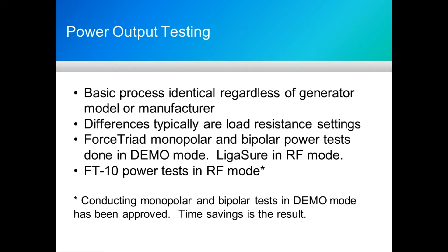And for the power testing, the basic process of the generators, regardless if it's a Covidien or an FX, they're all basically the same. The Triad monopolar and bipolar are done in the demo mode. LigaSure is done in the RF, and on the FT10, all power tests are done in the RF mode.